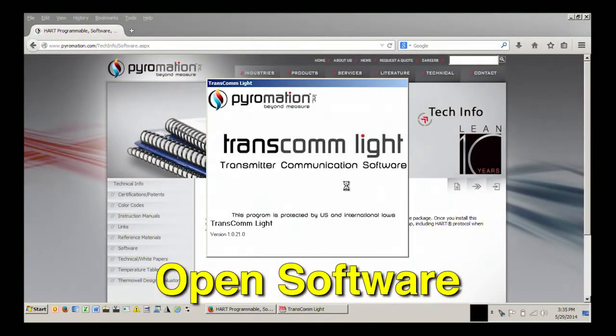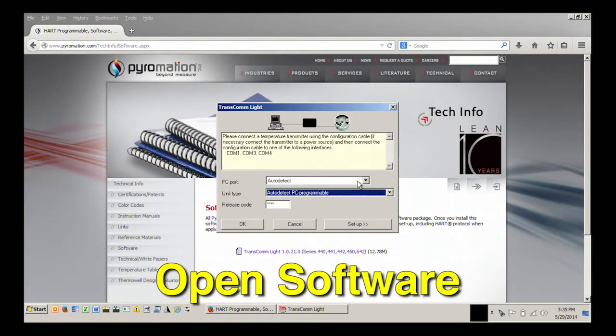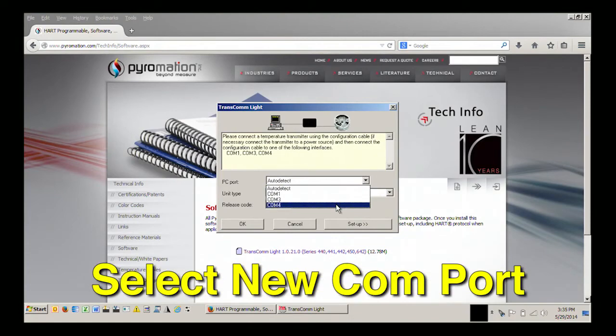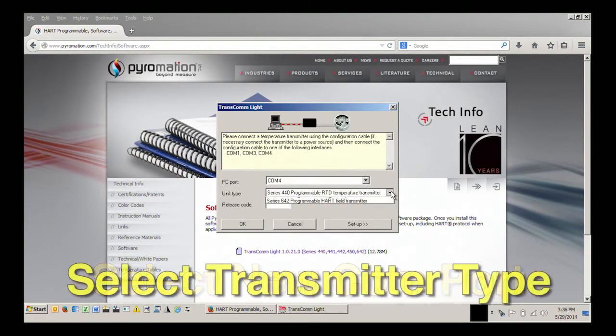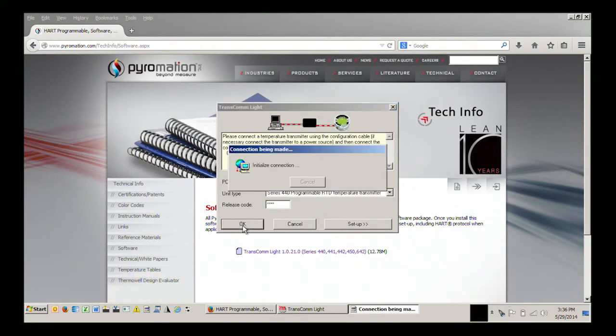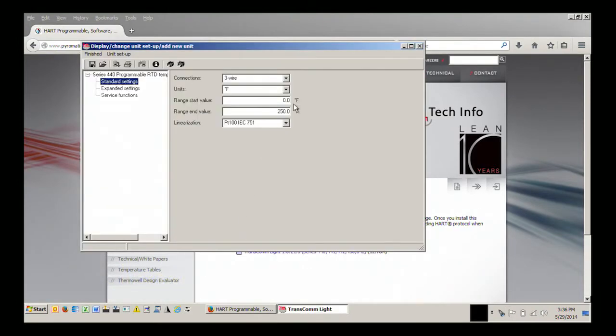Open the software, then select the new COM port that's available. Then select the transmitter type that you're working with, then hit OK. Once the software comes up, you can select between 2 and 3 wire circuits, Celsius and Fahrenheit. You can adjust the calibration range to whatever you desire. It is set up for only the PT100 per the IEC 751, which is a 385 curve.